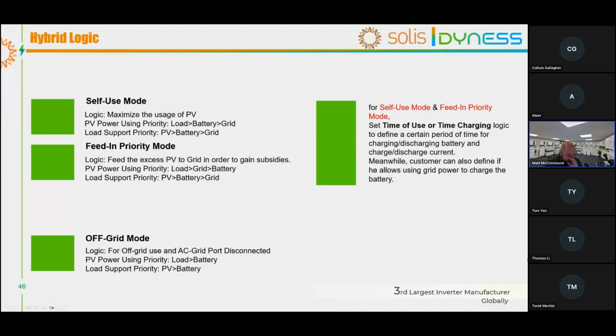And then when you're about to commission the inverter, our inverters can work in a few different modes. There are three main modes. The first one, which you probably see 99 times out of 100 in the UK, is the self-use mode. Basically its job is to use the meter information and then use as much PV as it can in order to save on your energy costs. So the PV supplying priority is that the PV will supply the load first, any excess goes to the battery, and if your battery is full, then it goes to the grid. In terms of load support priority, it's PV first, then battery, then grid. So if your load requires energy, it looks for the PV first, then the battery, then the grid.